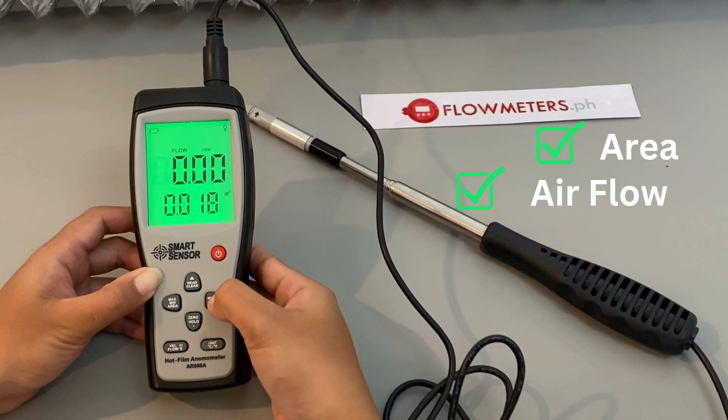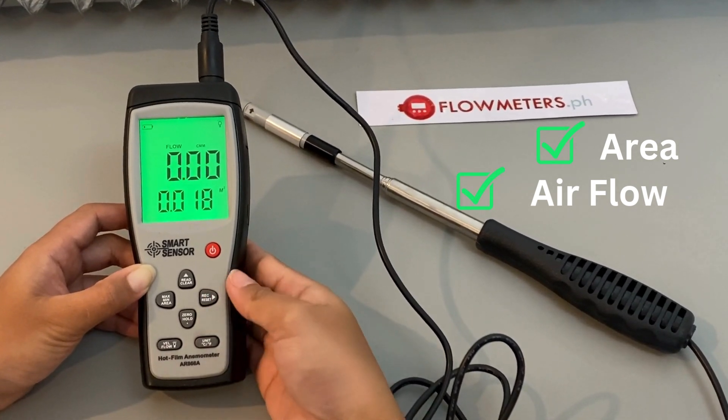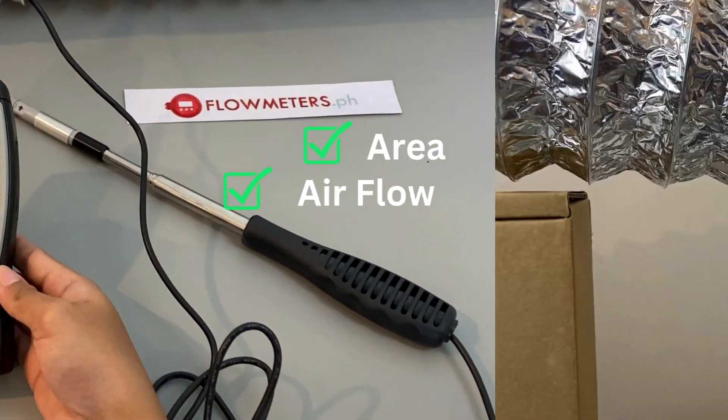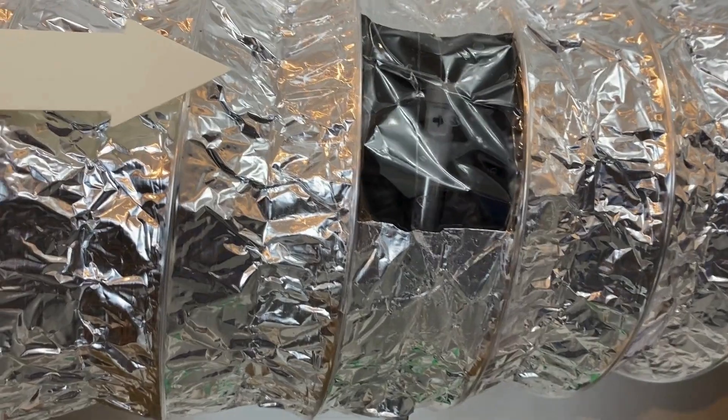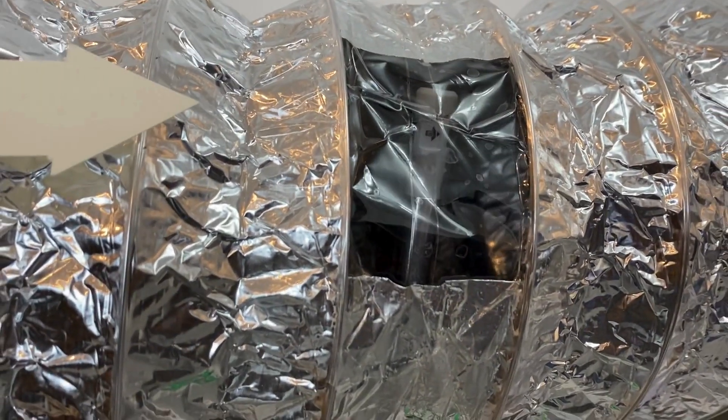Now that your area and air flow units are set, you're ready to test the air flow. Just remember to place the probe in the air flow with the air direction matching the direction of the arrow printed on the tip part of the probe.